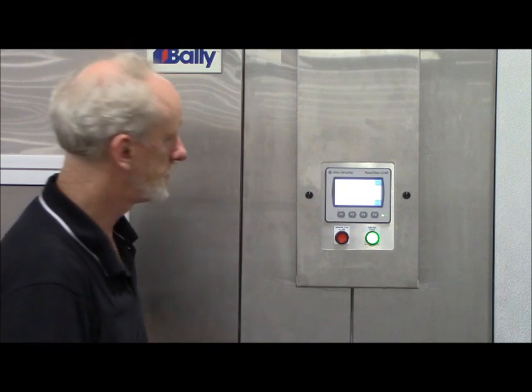So let's say you forget to put the product probe in the food. That probe is now in the air, so it will control the cycle based on the air temperature, not the food temperature. And as a result, the air temperature will only go down to 36 degrees, and you will lose your batch. So we programmed the controller to sense that the air temperature and the product temperature are too close together when you close the door. It displays a message so that you can either insert the product probe into the food or go into manual mode.